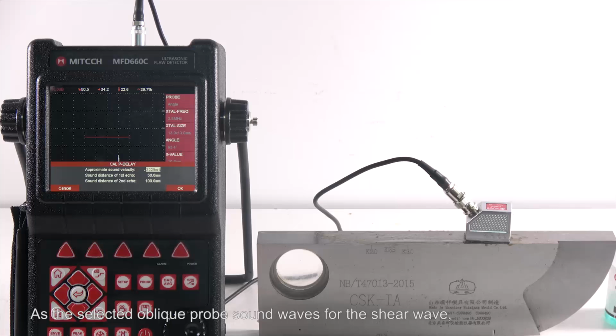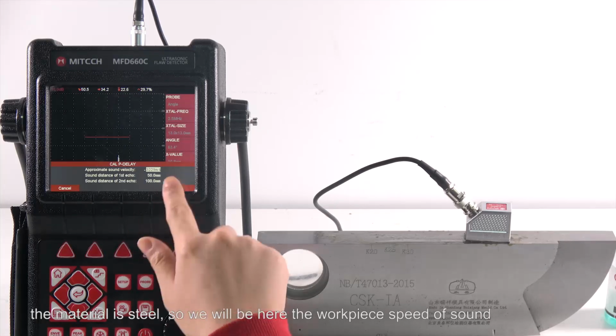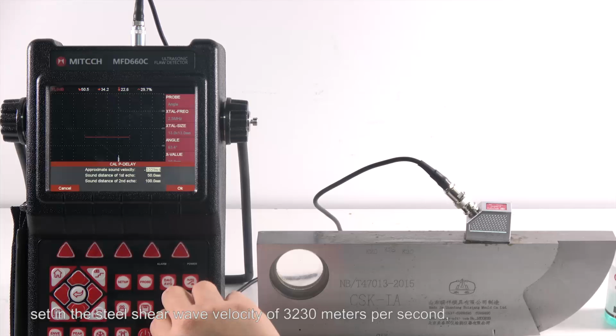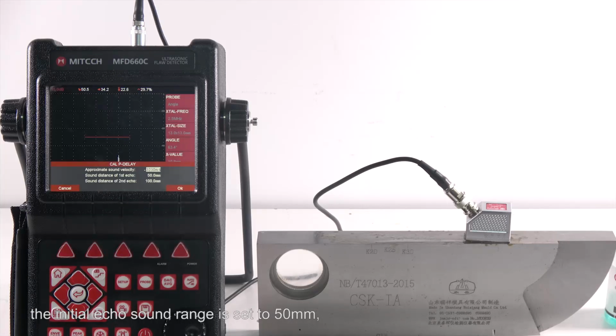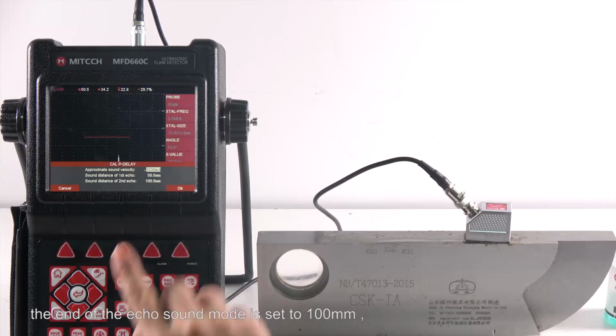The sound wave of the selected oblique probe is a shear wave, and the material is steel, so we set the workpiece speed of sound to the steel shear wave velocity of 3,230 meters per second. The initial echo sound range is set to 50 mm, and the second echo sound range is set to 100 mm.